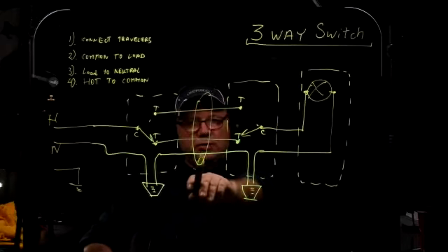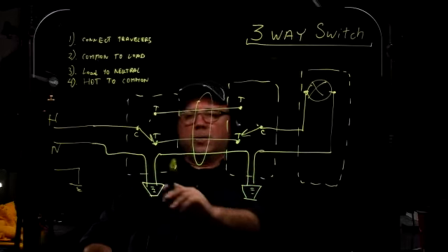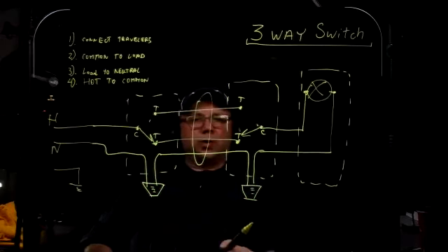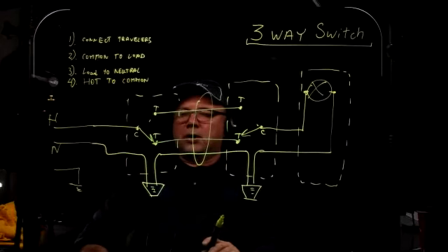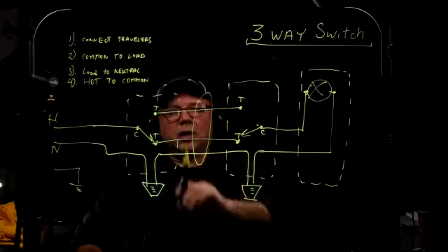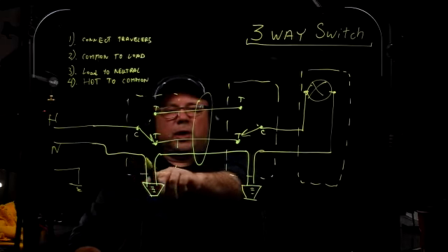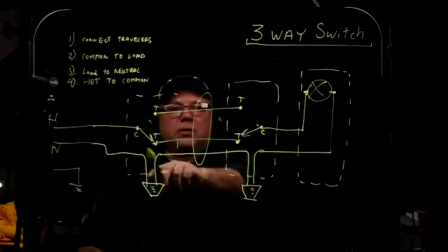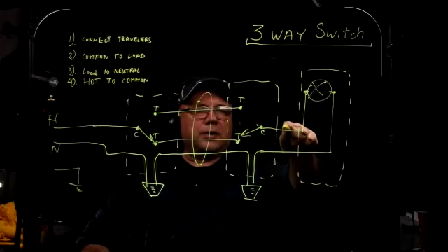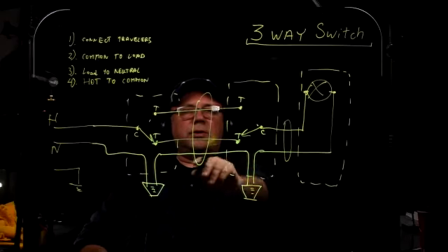But actually, yes, you do have the neutral, so we don't have to worry about pulling extra wire, because this box has a neutral, this box has a neutral, and this box has a neutral. And the grounding is going to be carried through the metal conduit, if it's a metal conduit, or it's going to have to be another green jacketed wire pulled in through the pipes if we're dealing with PVC conduit. Okay? And here's also a conduit. So in this conduit, we have 1, 2, 3 wires.